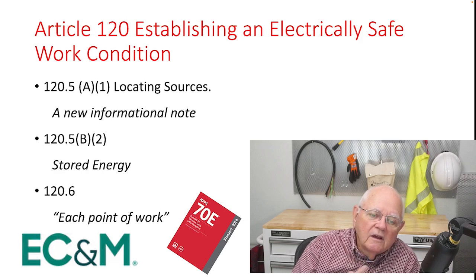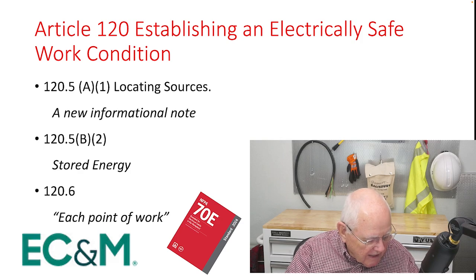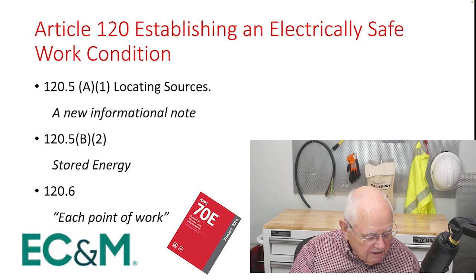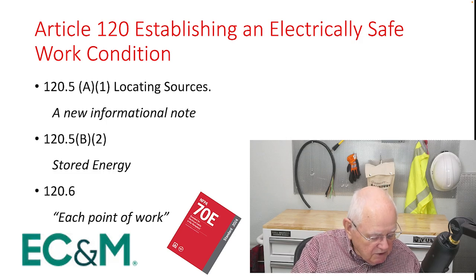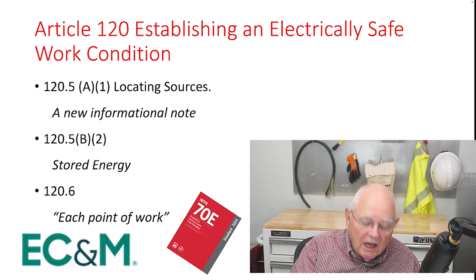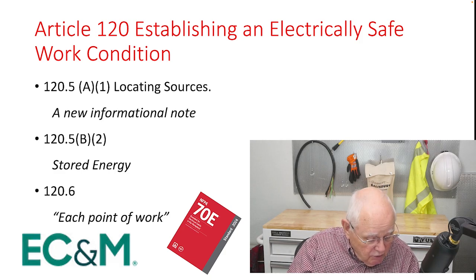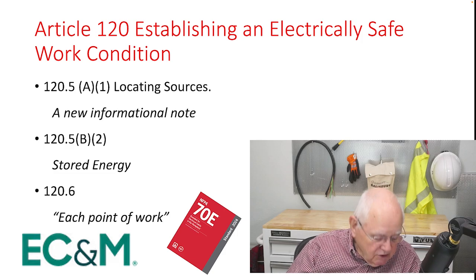120.5(B)(2) then, in that same section, addresses stored energy and particularly stored mechanical energy. There's a little rewording. It says, other sources of stored energy shall be blocked or otherwise relieved. And then the revision gives us a little more description: to the extent that the circuit cannot be unintentionally energized. Also, there's a new informational note that references you back to Article 460 on capacitors for stored energy as well.